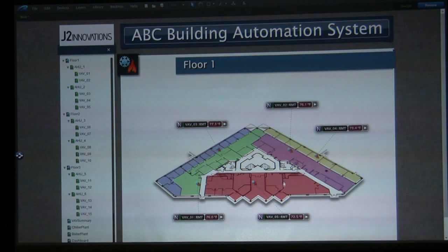Let's do a little bit of the pizzazz. So, mouse over. This is something that you see in high-end graphics. And to do this in Niagara, you kind of have to put a point over in Niagara, and you hope that your communications is fast enough so that when your mouse comes over the top, it kind of highlights. When we do things in Fin Builder, we decide what stays on the server and what should be optimized on the client, and mouse over clearly is one of those things that you would do on the client side.